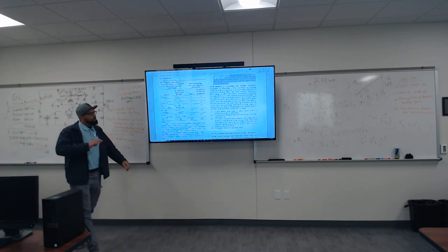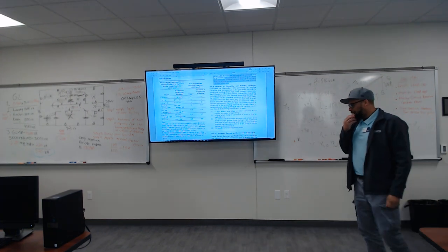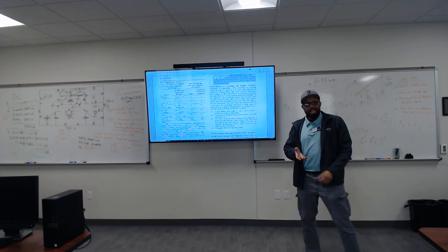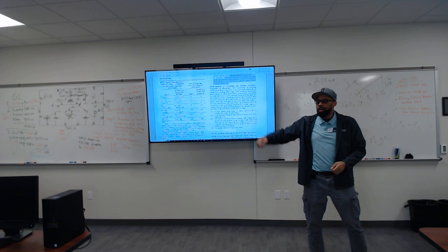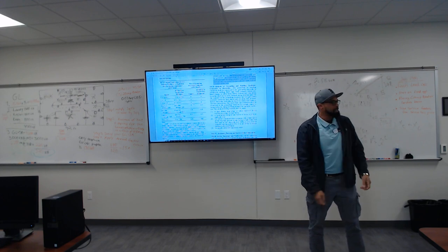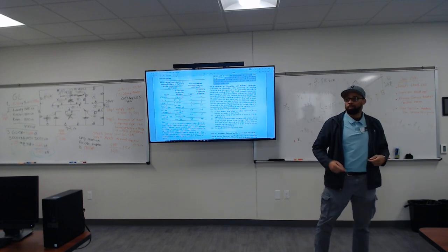The grounded conductor does. Now, you all are just jotting down information. I ain't had nobody ask, hey, Mr. Shields, why are these wires the same size and why do you have two different tables, one that says ED, one that says ING? Let me explain. All right, the grounded wire is the return of the neutral path. You send out, just like a baseball, the batter hits it, it's got to come back where he started from, just like current.